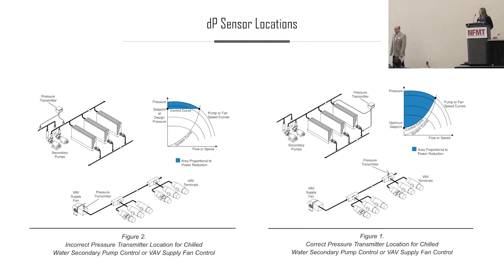So if we can actually take the time and effort, and this does cost a little bit of money on this one, but not a lot, get the sensor out at what we'll call the far end here, at the furthest branch, the furthest served equipment, get the delta P measurement there and set our set point off of that. It allows the VSD or the BAS to control across a much wider portion of that fan curve or pump curve. And that blue area represents the potentials for your energy savings. And so there is a combination of move the sensor and then find what that new measuring point ought to be.